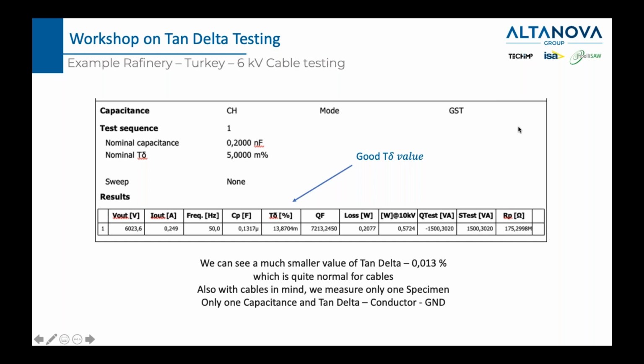I'm not sure I understand. So with sweep frequency, you get discrete steps and the value of tan delta. You don't get any mean values, just discrete steps. And Mr. Mohatni is asking what frequency range is to be applied in frequency sweep test. Well, you can do, let's say, 20, 35, 50, 75, 105, 135, 205, 305, 400, something like that.